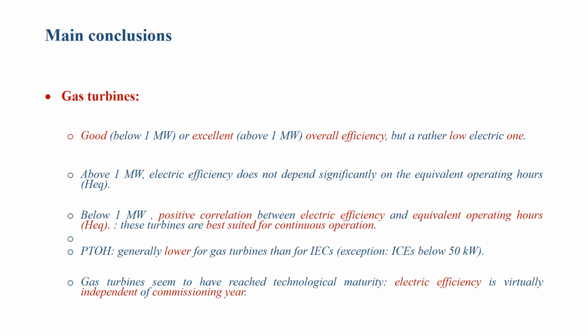So these turbines can be used for intermittent operation if needed, up to a point probably. This is not the case below 1 megawatt, because below that we have a positive correlation between electric efficiency and equivalent operating hours. So the smaller turbines, below 1 megawatt, are best suited for continuous operation; you should not use them for intermittent operation.